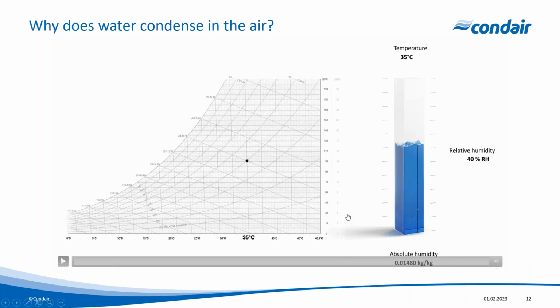And when we look over to the left-hand side, we've got a psychrometric chart. And just to take you through the basic elements here, at the bottom we've got our temperature going in degrees C, up from 0 up to, in this case, 50 degrees C. And you can see the relative humidity in these curves. That's 10%, 20%, 30, 40, right up to saturation point. And our air is sitting just around here, 35 degrees C, 10, 20, 30, 40% RH. And we've got a moisture content of 14.8 grams.